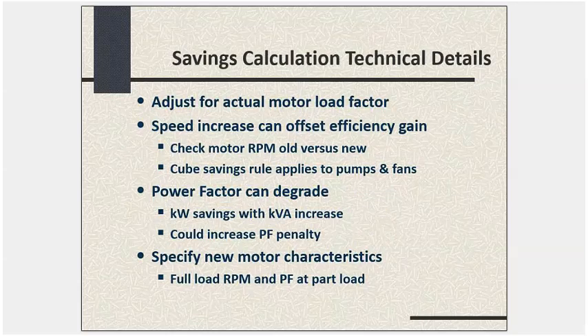So here's just some savings calculation technical details, especially for motor loads. You've got to consider what the motor load factor is. If you just go in and assume the motor is loaded to 75%, but it's actually only loaded to 60%, and then you try to calculate your savings with that assumption without actually assessing the motor load, you'll make a mistake because you're going to overestimate savings potentially by overestimating the load on that motor.